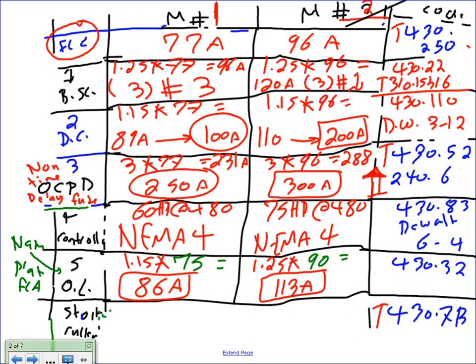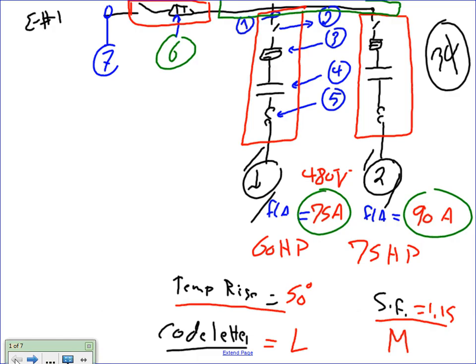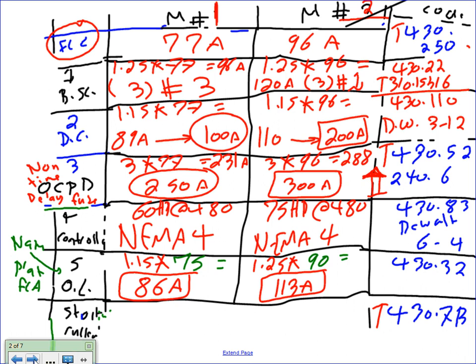That 75 is not a full load. This is the full load amp from the nameplate. Oh, okay, from the nameplate. Given. Only for the overload, guys, we always use the nameplate. For everything else, you use the NEC code value, which is the one we calculated right here at the top, the full load current. Only for overload, or if it says here nameplate full load amp. Please write yourself a note right here: nameplate full load amp.